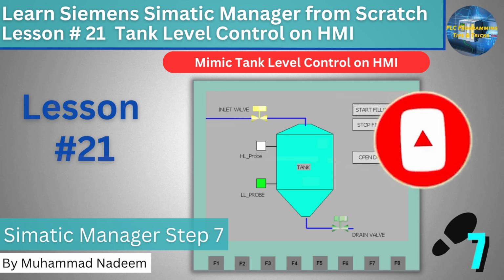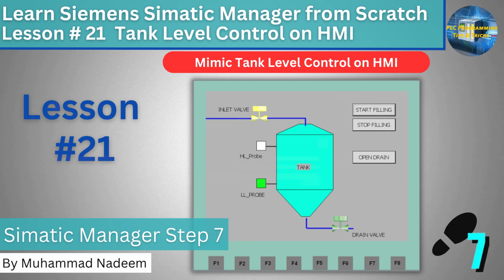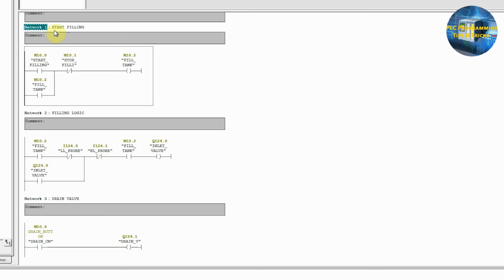Now let's see the PLC logic for this tutorial. In network 1, we have a tank filling logic. We have a bit M10.0. Whenever this bit is on, it will turn on the tank fill bit M10.2. And this bit M10.2 will be latched on through its own normally open contact through this route.